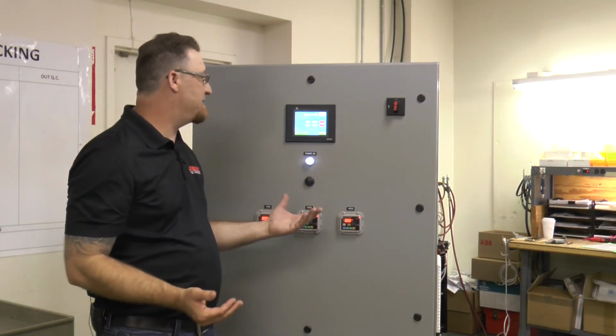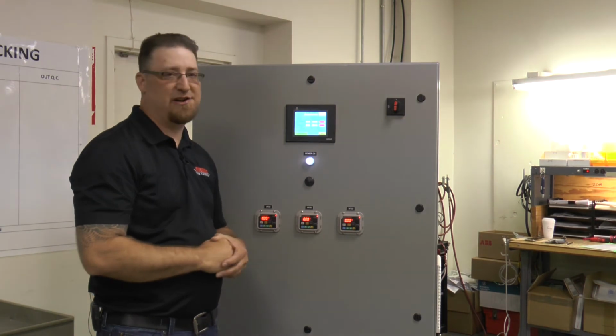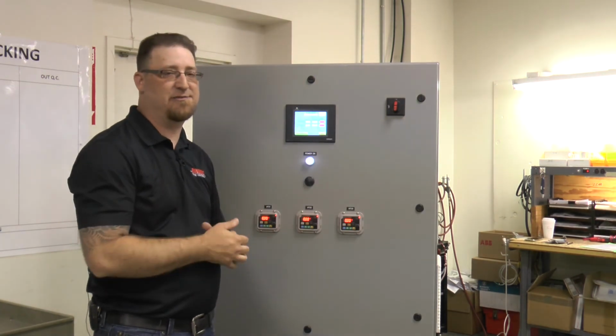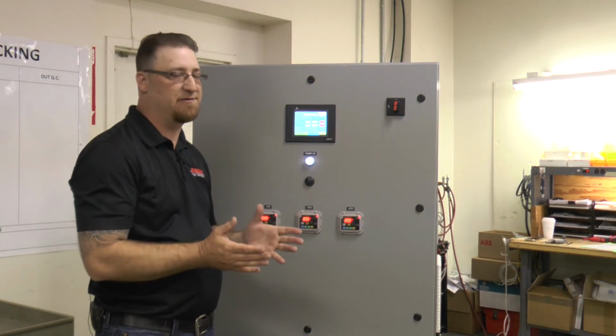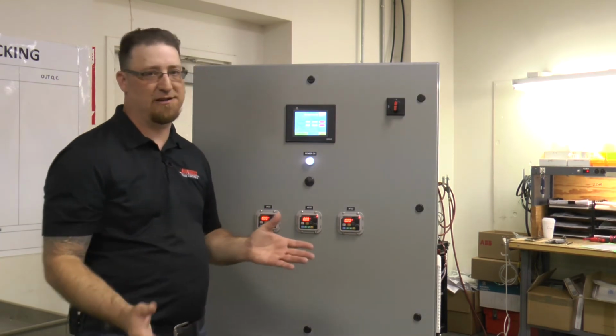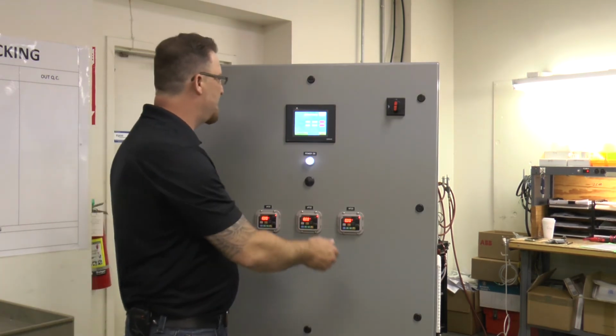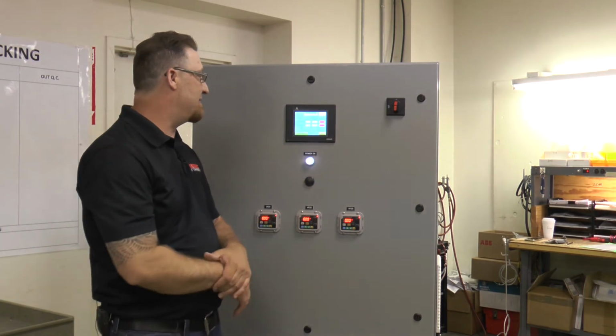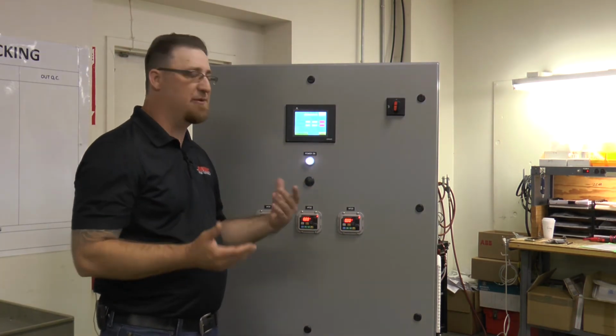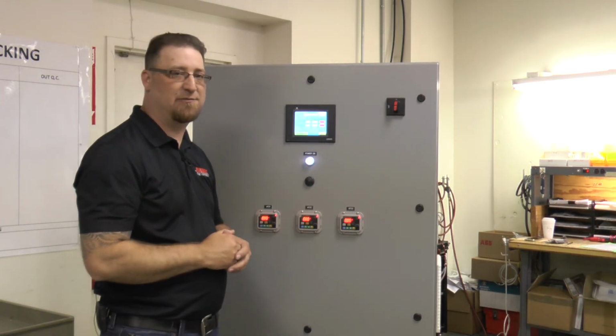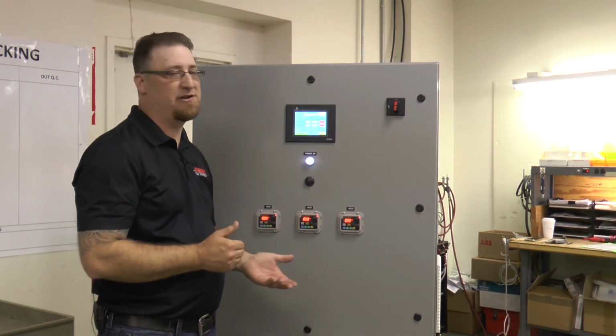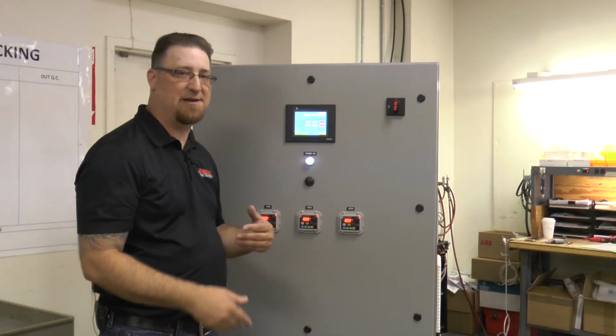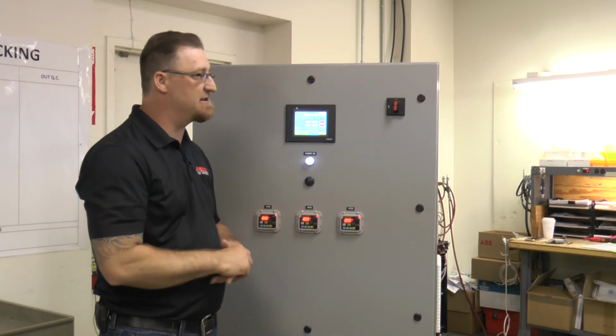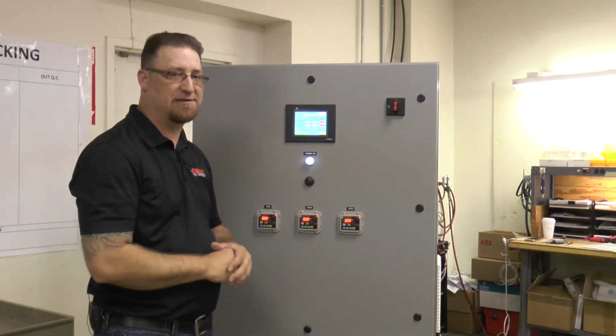High discharge pressures, same functionality. This is just on the high end if you get too much pressure. At which point do you set an alarm, and how long do you want to wait before that alarm goes off? And you also have a reset button. So you can either do a manual reset where you have to press an alarm reset button, or you can have an auto reset, which after a certain amount of time it'll auto reset and the system will go back in automatic and it'll start pumping again.